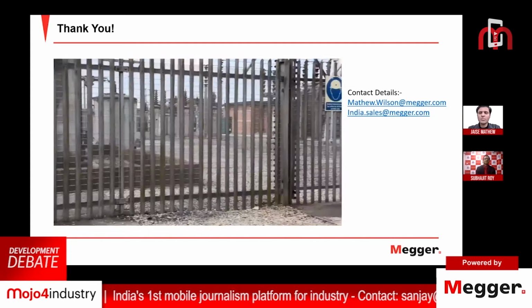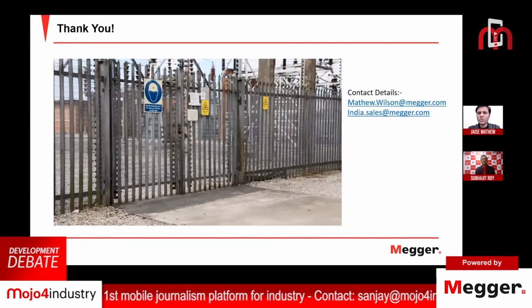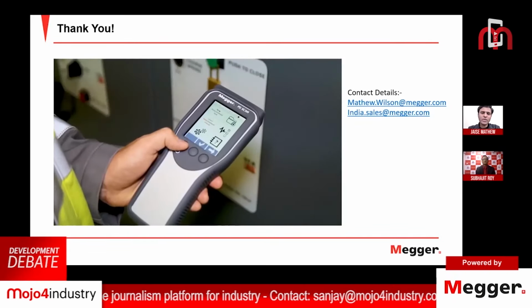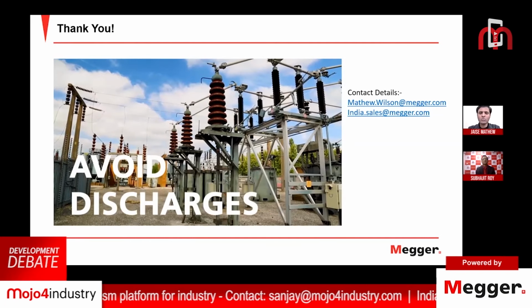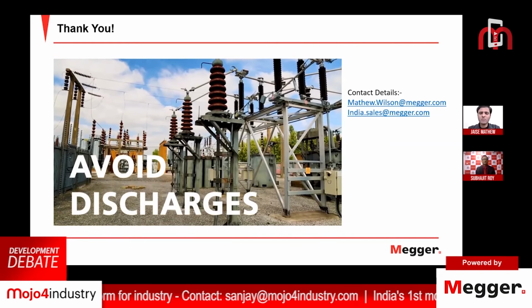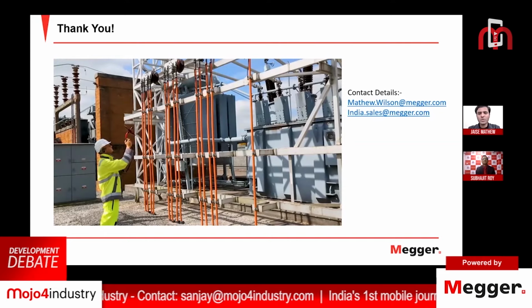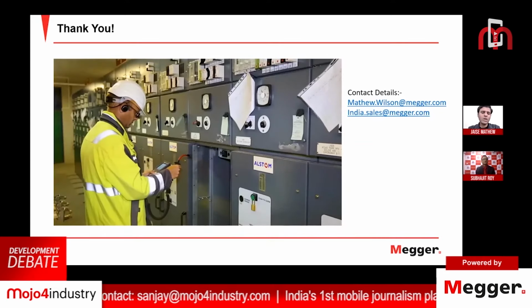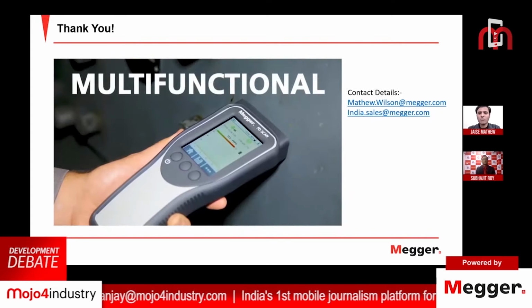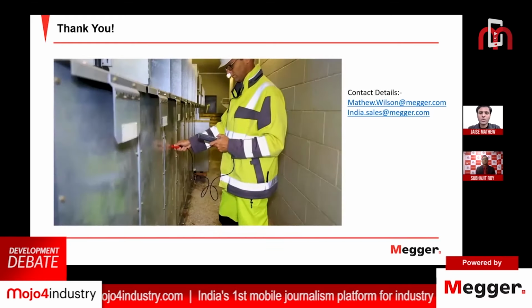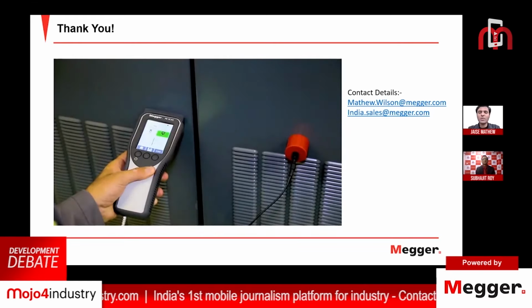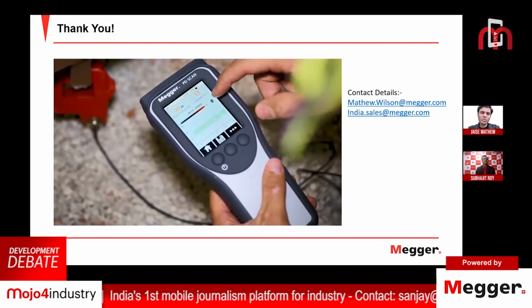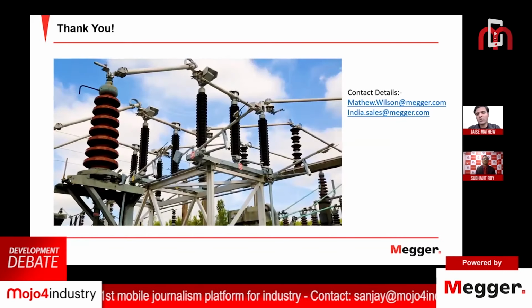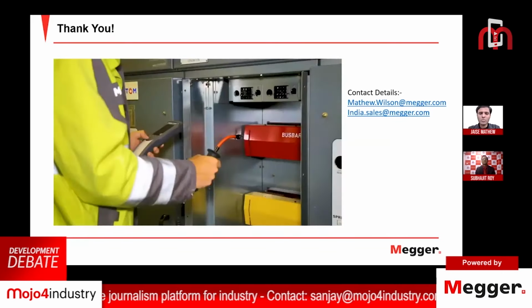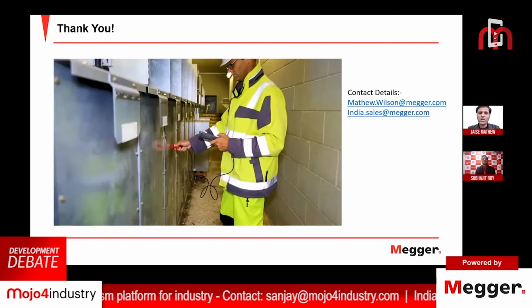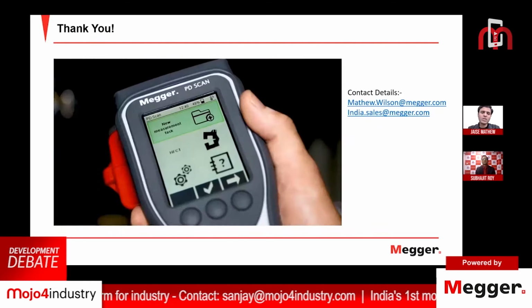We, as Megger, are giving a complete solution for each and every electrical asset monitoring. If you have a circuit breaker, there are preventive maintenance test equipments for the circuit breaker. For transformers, we have nine to ten equipments to test the different components of the transformer. For relays, yes, we have smart testing equipments. For cables, yes, we have cable fault locating as well as predictive cable diagnostic equipments.